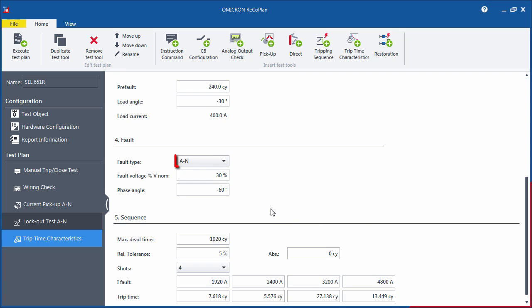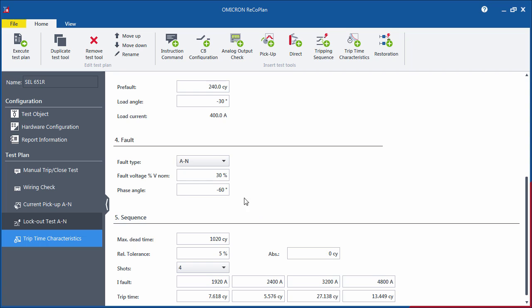In a similar way to the other test tools, the Fault section contains the fault type and the voltage output specification during this state. Just set the controls to realistic values, for example, 70% of the nominal voltage and a phase angle of 60 degrees.